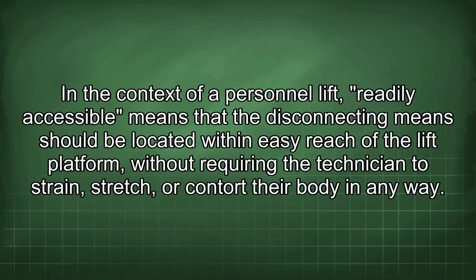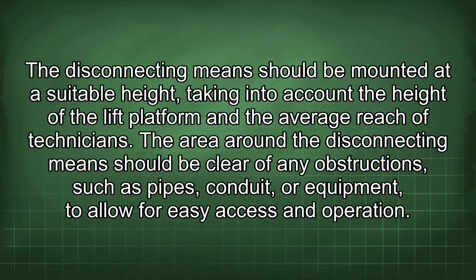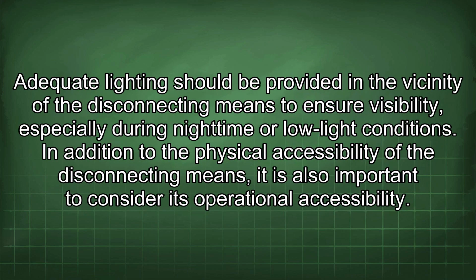In the context of a personnel lift, readily accessible means that the disconnecting means should be located within easy reach of the lift platform without requiring the technician to strain, stretch, or contort their body in any way. The disconnecting means should be mounted at a suitable height, taking into account the height of the lift platform and the average reach of technicians. The area around the disconnecting means should be clear of any obstructions, such as pipes, conduit, or equipment, to allow for easy access and operation.